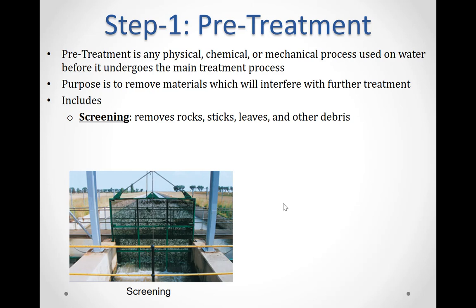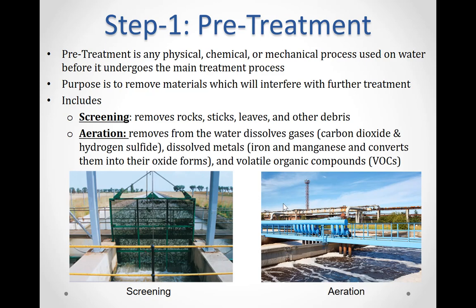Screening stops any large debris from traveling into the intake pipe using coarse filters and bars. Aeration is a treatment step that removes dissolved gases such as carbon dioxide and hydrogen sulfide, as well as dissolved metals such as iron and manganese, converting these dissolved metals into their oxide form. Pretreatment can also remove volatile organic compounds, or VOCs.